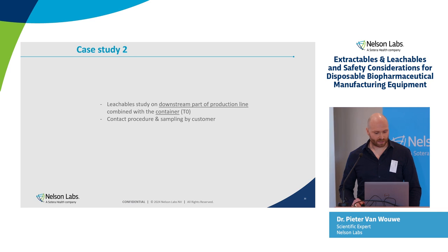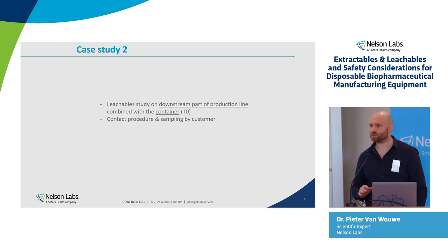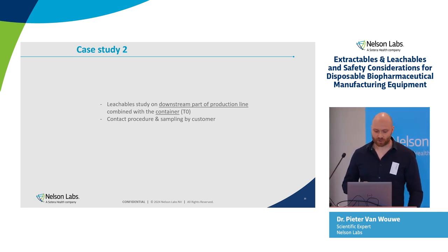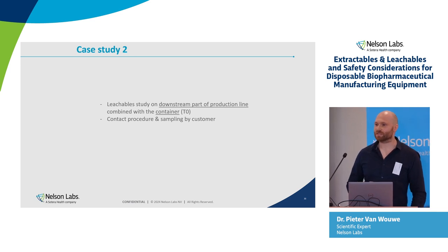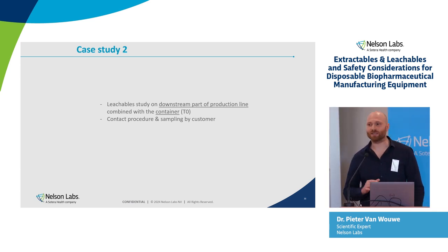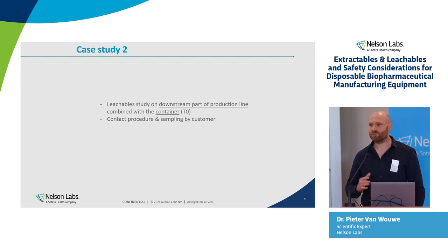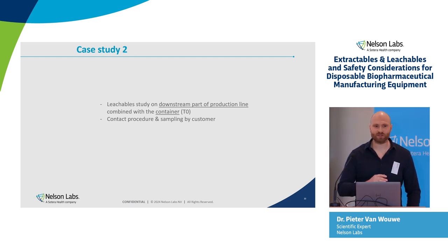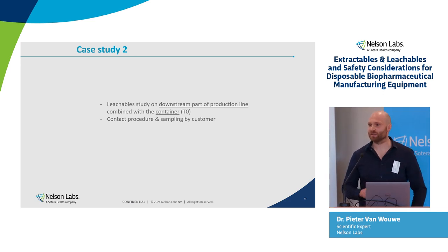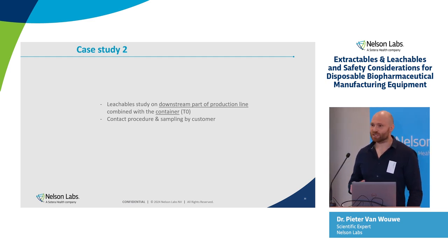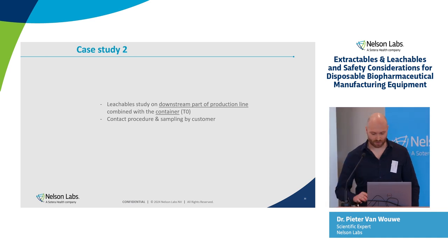A big difference here is that the contact procedure and the sampling was performed by our customer. And that is a big difference with, let's say, a traditional leachable study on a container closure system, because there we often do the aging at Nelson Labs in a climate chamber. We take the sample. For IV bags, most often the customer does the aging, but they will send the filled bags to Nelson Labs and we open the bags and do the sampling. But here, the contact procedure and the sampling are under the responsibility of our customer.